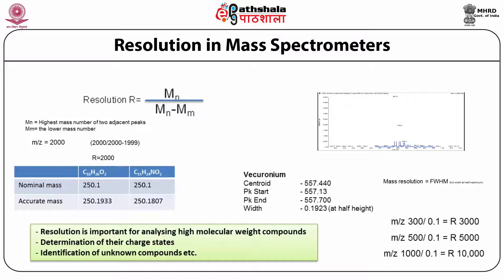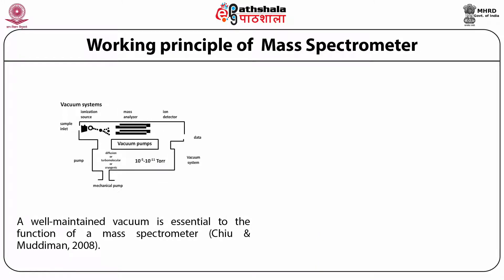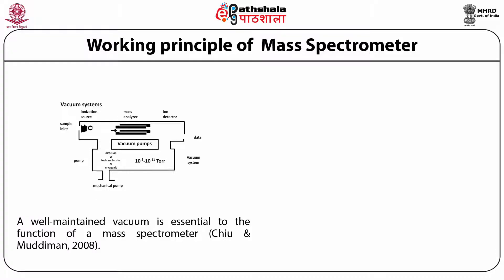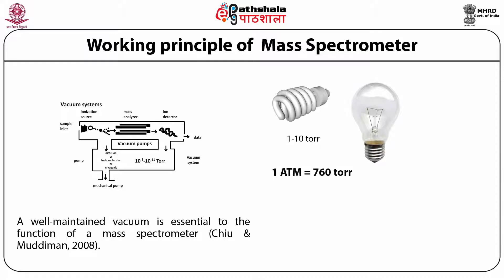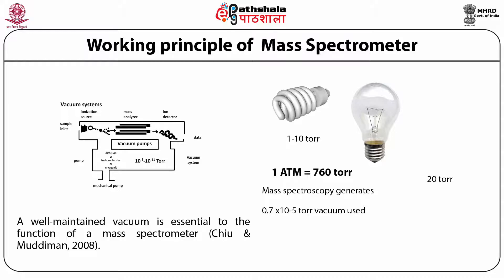Resolution is important for analyzing high molecular weight compounds, determining their charge state, and identifying unknown compounds. Now, looking at the working principle inside the mass spectrometer: the instrument is kept in very high vacuum. By comparison, a fluorescent tube light uses about 1 to 10 Torr vacuum, whereas for mass spectroscopy the vacuum required is 0.7 × 10⁻⁵ Torr — a very high vacuum essential for ions to travel and be analyzed.